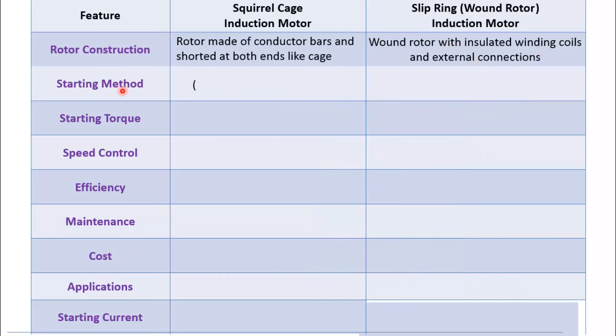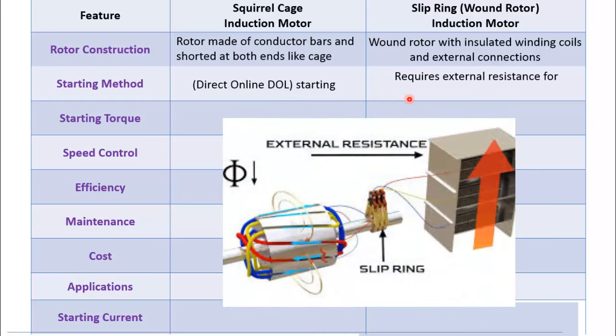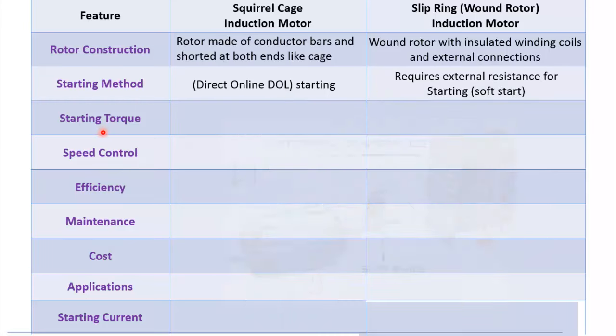The starting of squirrel cage is simple, for example direct on line starting. Whereas, the slip ring motor requires external resistance for soft starting. Starting torque of squirrel cage motor is lowest compared to slip ring motor.